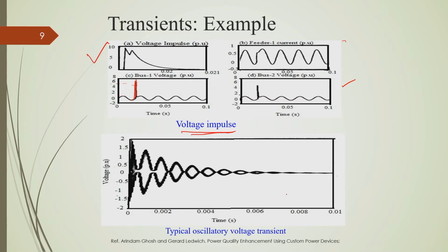Similarly, this is an example of oscillatory transients, which cause some decaying term. They last for some period of time, then after that they go to the steady state value. Here the voltage magnitude in per unit is given, not the voltage waveform as such. It has an oscillatory transient, first a few cycles of very high magnitude, but not as high as the impulsive transients. They may be twice the nominal peak value of the supply voltage, but they take a considerable amount of time, in the range of milliseconds, to die down.